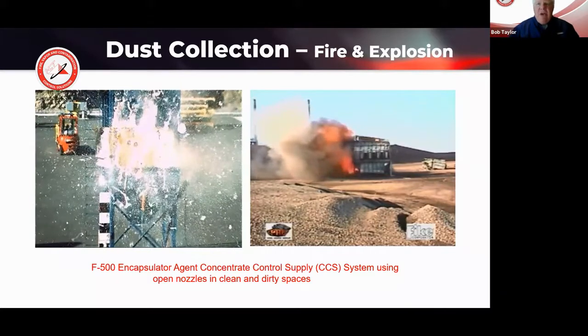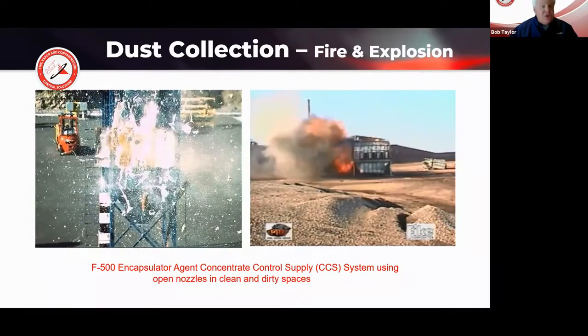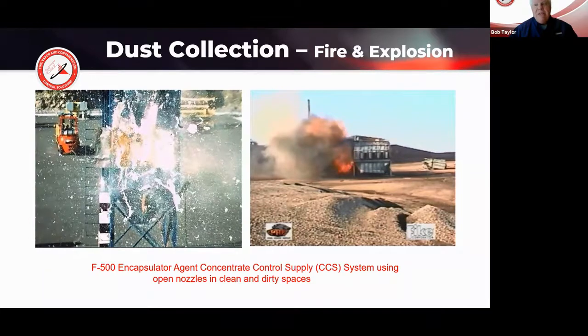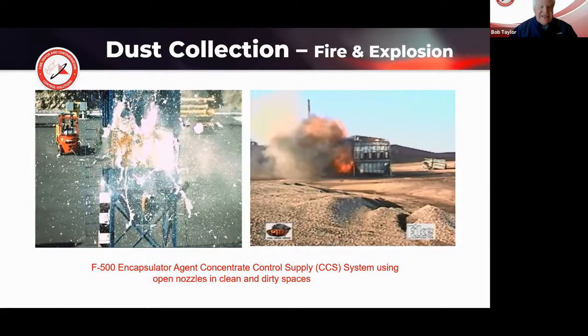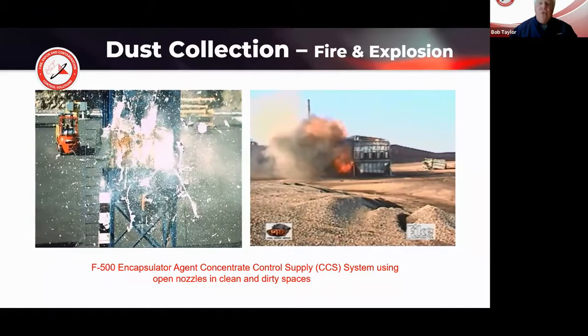The F500 encapsulator agent concentrate control system, commonly known as a CCS system, is often used in dust collectors across all fuel types, using open nozzles in both the clean and dirty space. We work with fire protection engineers to design concentrate control supply systems, introducing the F500 encapsulating agent for the most effective results, working on all chemical and molecular levels for the greatest efficiency.